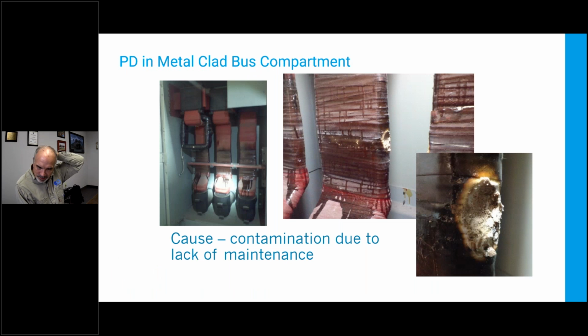Here's an example of someone who just didn't clean the switchgear. This was in Florida in a high humidity, high dirty environment, and this brace was there to keep this bus bar from pretzeling if there was a fault. And what happened is they didn't clean it, and these horizontal surfaces between the phases collected dust. The dust collected humidity, became conductive, changed the electric field distribution, and caused this massive discharge.